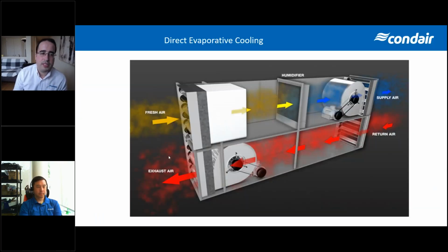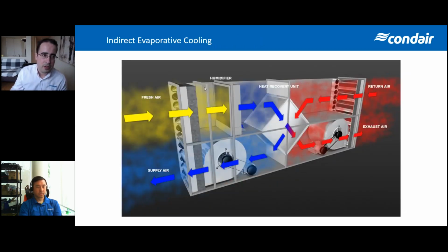So when you install evaporative systems, there are, let's say, 3 different ways you can install. You can have a direct evaporative cooling, so you humidify or you cool the air, so you increase both your humidity and you decrease your temperature, and you supply directly to the room. You can also have indirect evaporative cooling, where you're gonna cool the outside air, and then you have heat recovery that will cool the return air and send it back to the room. So this way, the benefit is you don't humidify the air, you just cool the air. So if you don't want to increase your humidity, but you still want to use the benefits of adiabatic cooling, you can also use this type of application.